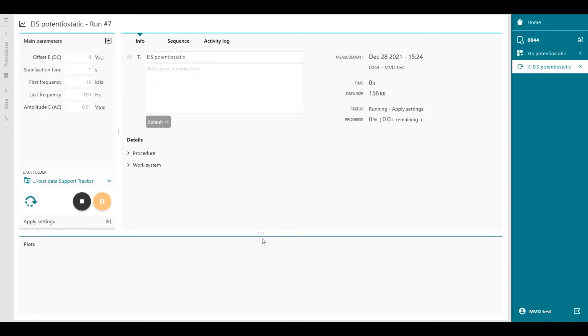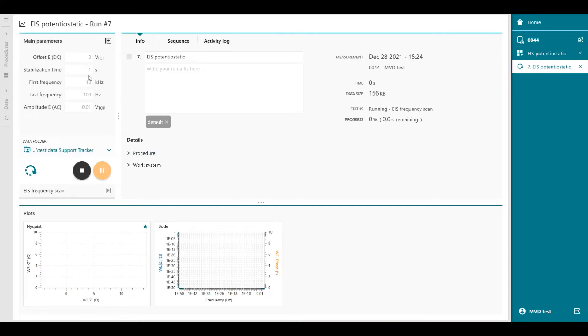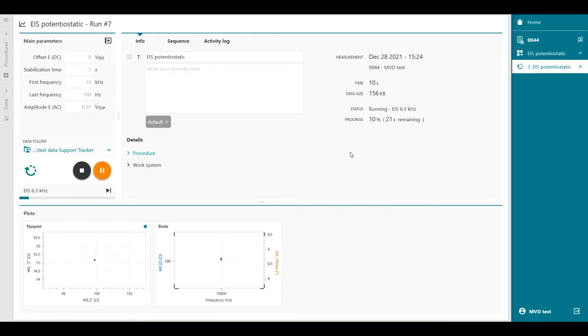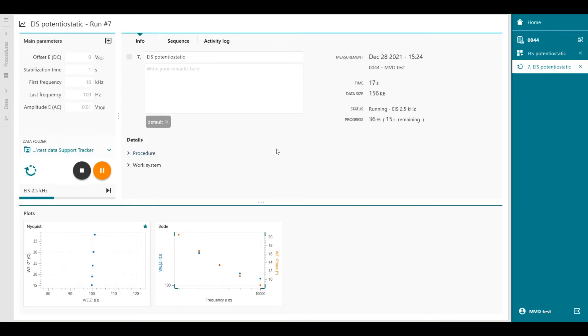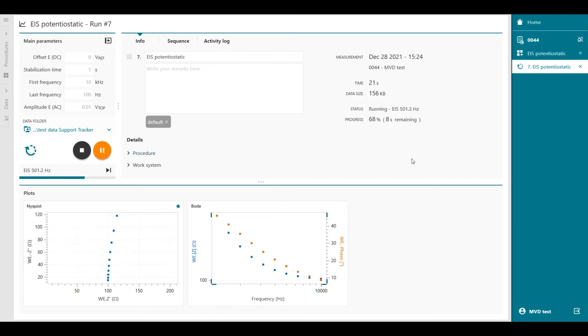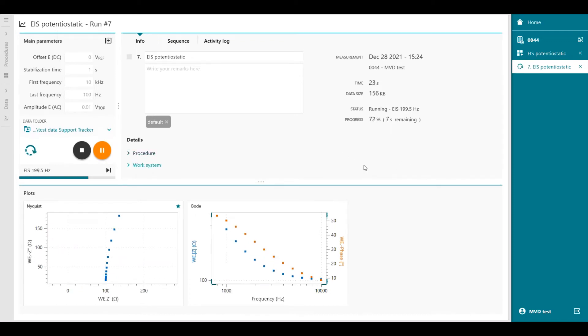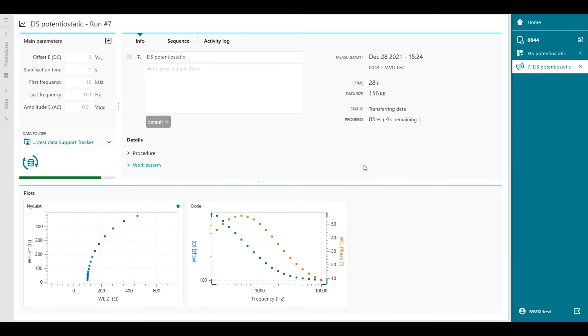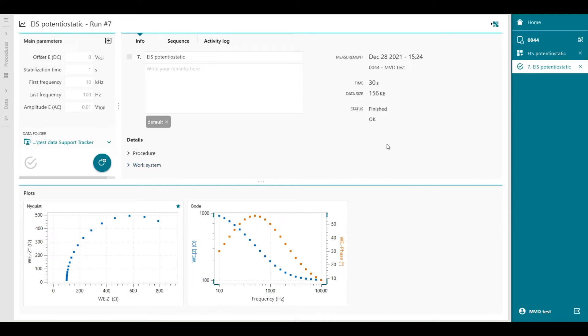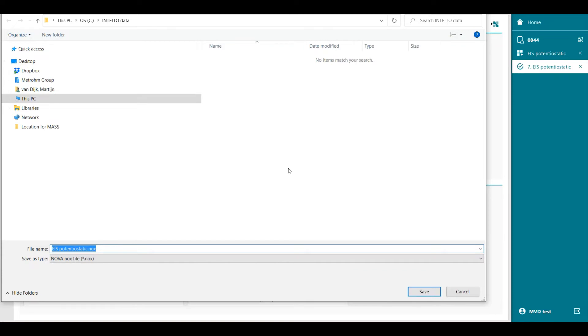This will take a few seconds because we scan from 10 kHz to 100 Hz with 10 frequencies per decade, so not that many data points. After the measurement is finished you will find here in the right upper corner the analyze data in Nova button. If you click on this button, first you have to save the experiment. The data is saved as potentiostatic.nox — an NOx file which can be read by Nova.